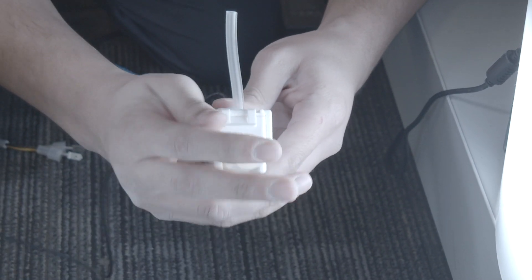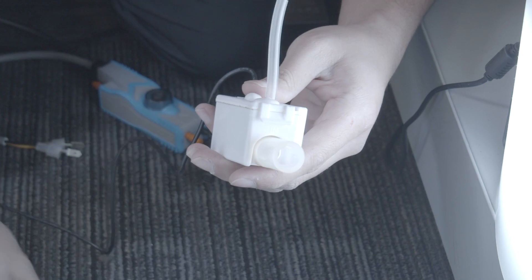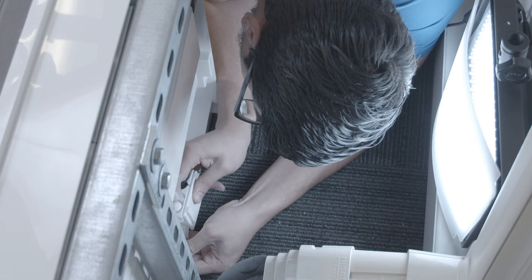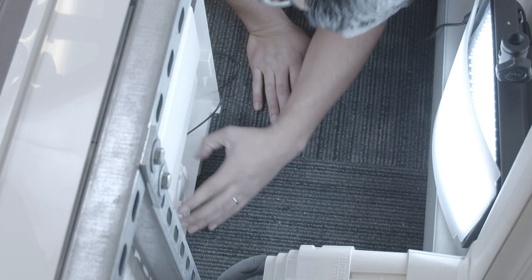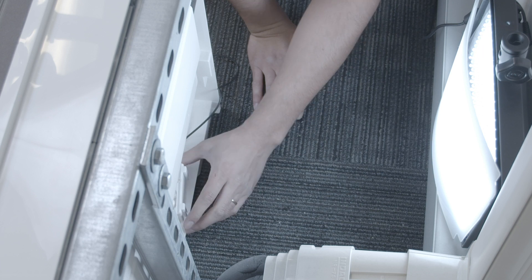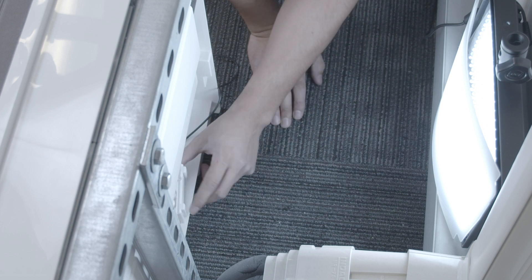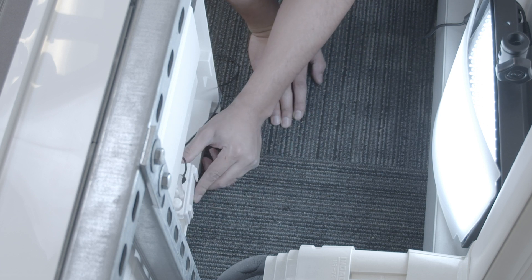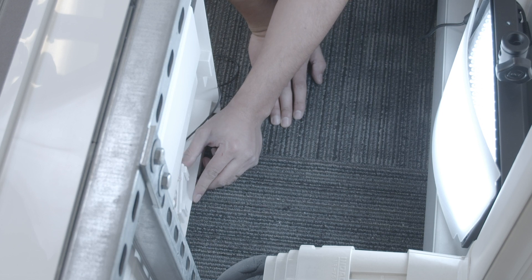Now, you can connect the reservoir to the factory provided drain hose located behind the unit. Make sure the reservoir is oriented in an upright position. If the reservoir is installed upside down or on its side, the pump's alarm will trip immediately after powering up.